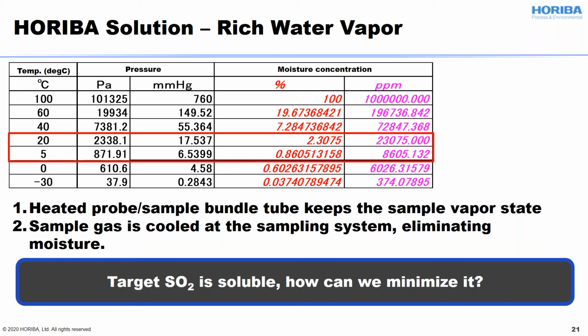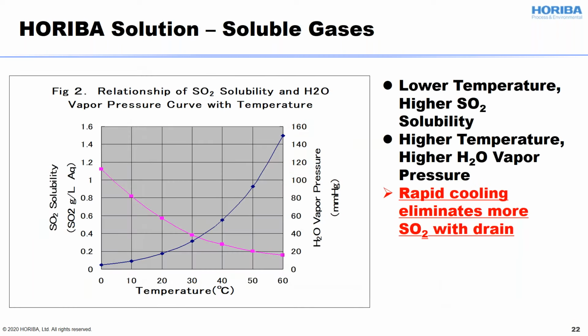But sometimes somebody may ask, you want to measure SO2, but SO2 is very soluble, so the measurement data for SO2 from your device could be less. So what are you going to do? Yes, that's true, but that's why we need to minimize the dissolving of SO2 while the SO2 gas is traveling from the sample import point to the analyzer. I will explain how we do that. So let's talk about how SO2 can dissolve into water.